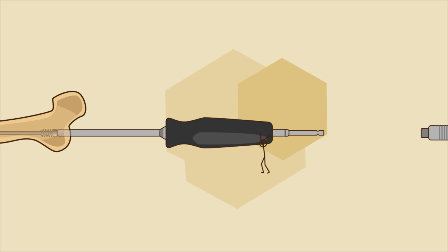Step 7. Attach the torque handle and apply counter-clockwise rotation until the limit is reached. A click sound will be heard. Remove the torque handle. Step 8. Unscrew the female component and pull to remove it from the bone.